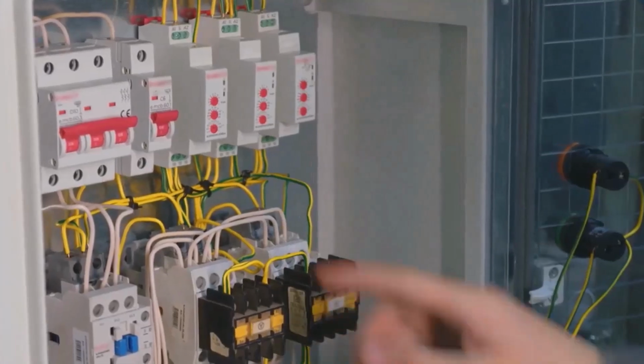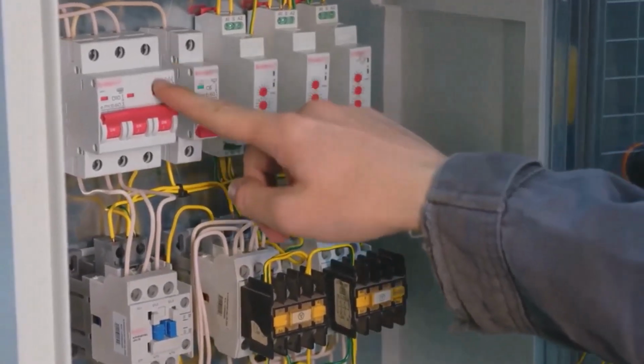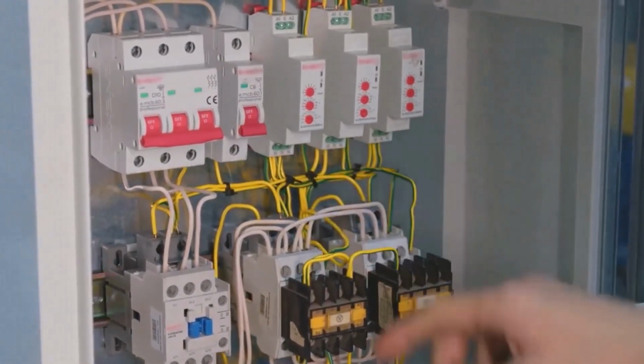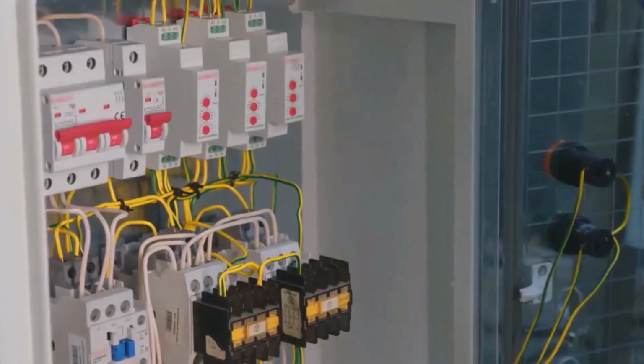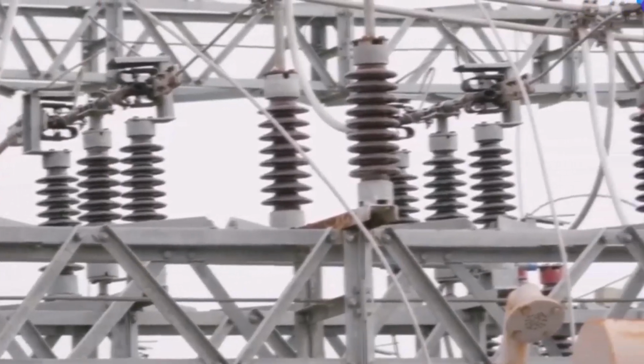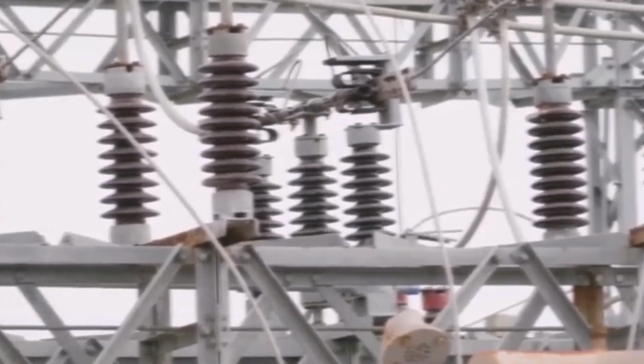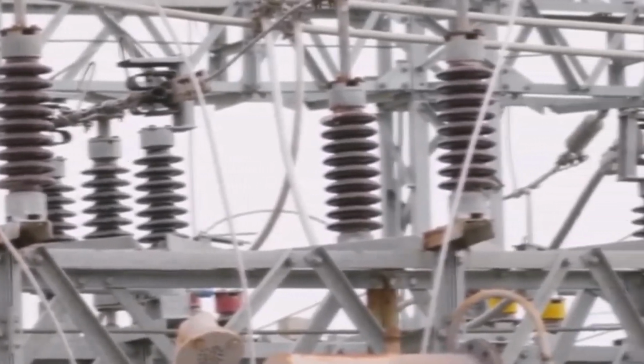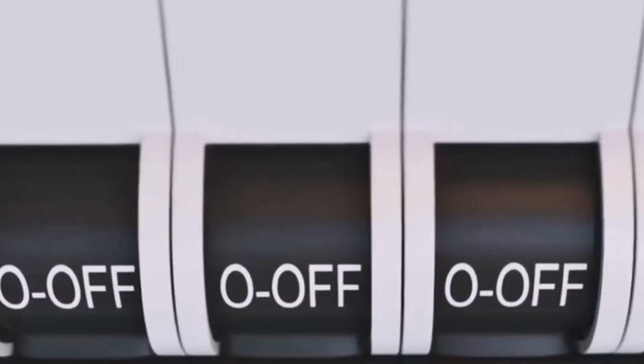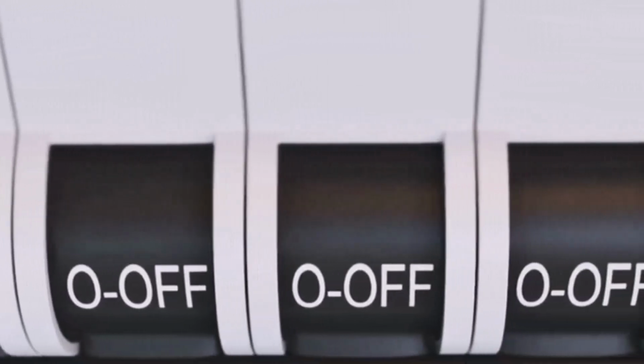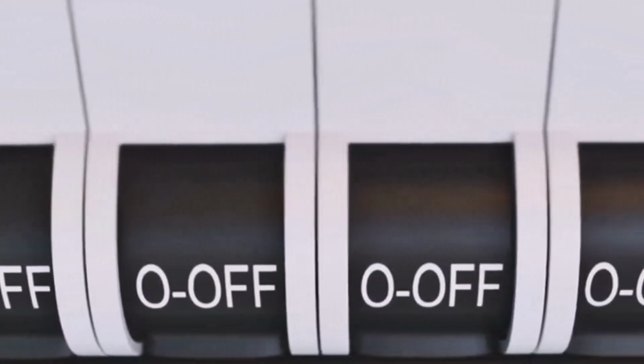Confirm all switches, isolators, and breakers are off. This is your safe starting point. Never assume, always check for yourself. Visually check for open gaps in isolators, making sure there's no chance of accidental connection or current flow. Double-check the off positions on all breakers, confirming that every switch is exactly where it should be before proceeding.